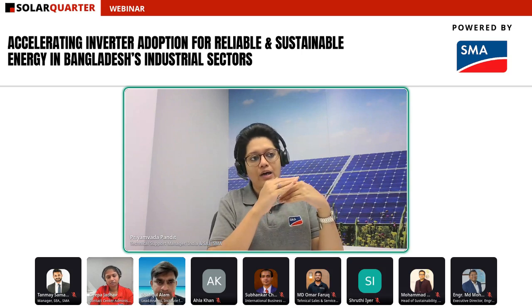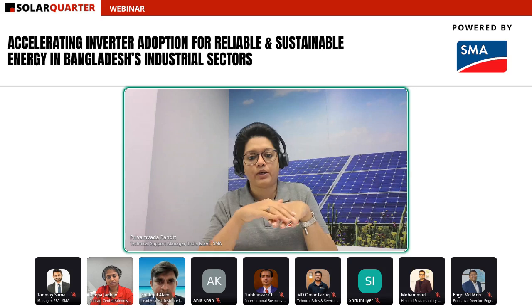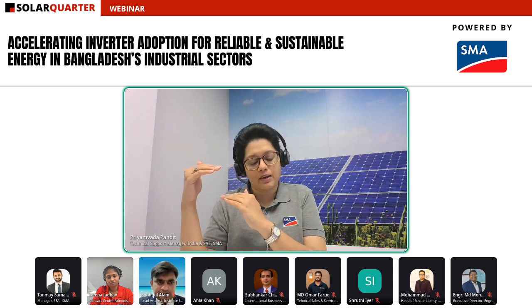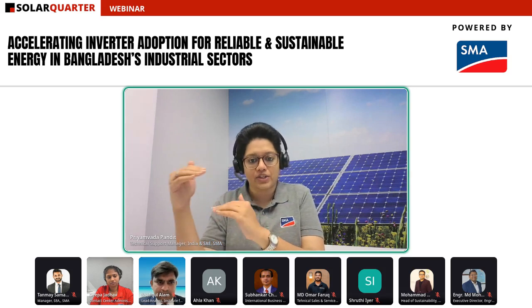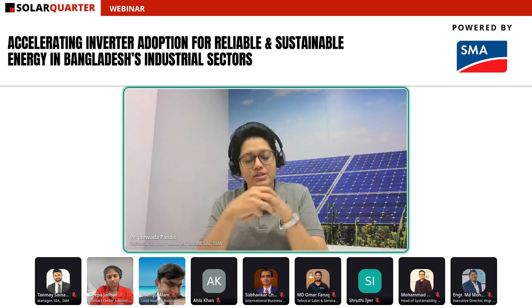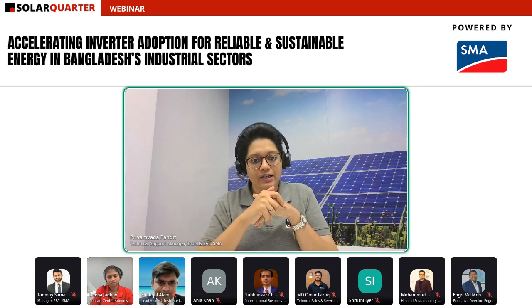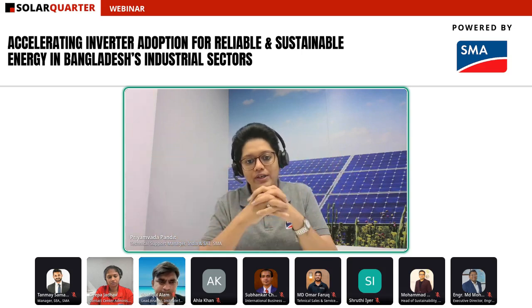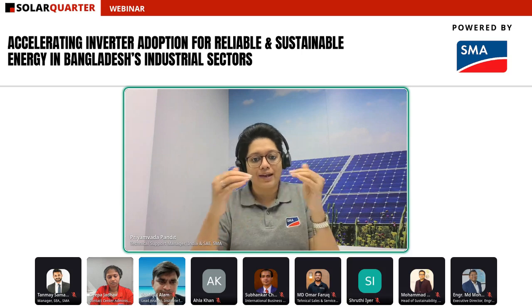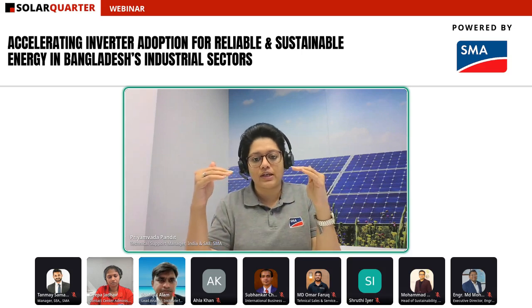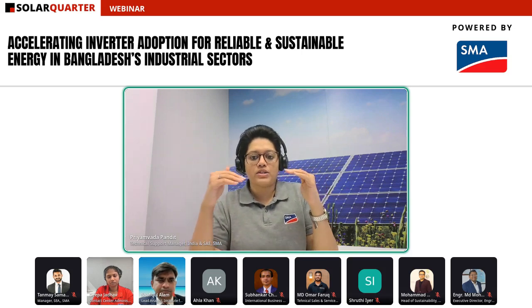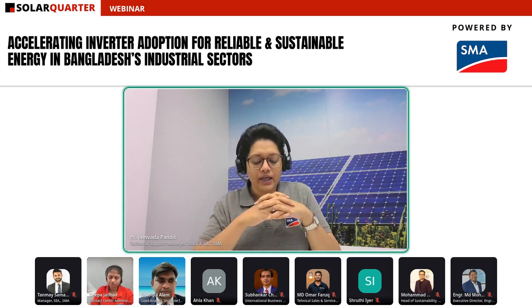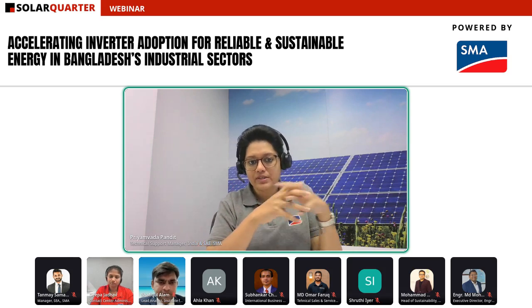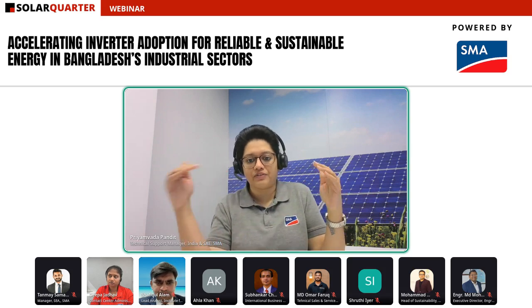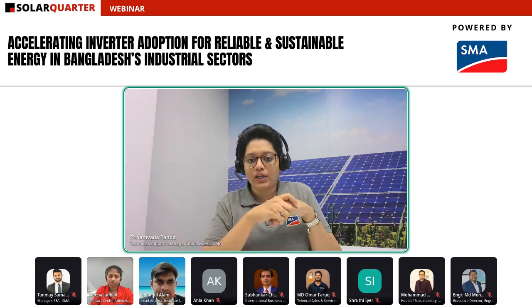difference between how solar works as compared to how other generators like diesel generators, or the grid, work. Typically diesel generators and the grid, or any rotating generator, will run at the power depending upon how much is the requirement, or how much is the connected load. So if, for example, right now my load requirement is only 50%, my generators will run at 50% only. But for solar, that does not happen.